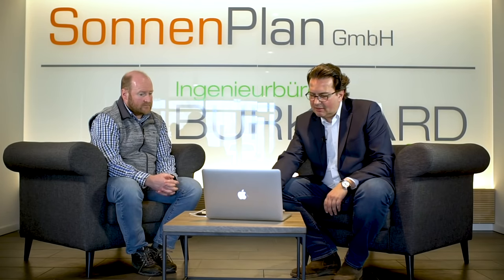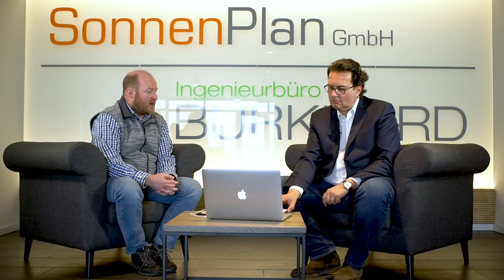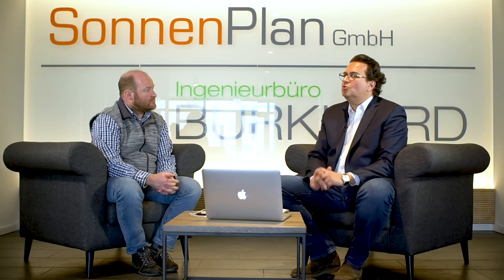Manuel Grimlowski fragte: Schaffen Wärmepumpen im Winter tatsächlich aus einer Kilowattstunde Strom drei Kilowattstunden Wärme? Gibt es saisonale Unterschiede? Bei einer Sole-Wasser-Wärmepumpe mit Erdbohrung hängt die Effizienz quasi nicht von der Außentemperatur ab. Bei Luft-Wasser-Wärmepumpen dagegen schon. Man muss in die Datenblätter schauen, ab wie viel Grad man unter den Faktor 3 kommt. Richtig gute Maschinen kommen noch bei Minustemperaturen auf den Faktor 3.